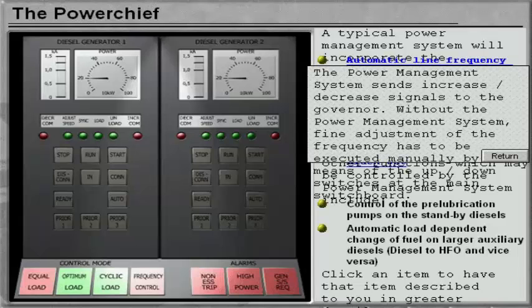The power management system sends increase and decrease signals to the governor. Without the power management system, fine adjustments of the frequency have to be executed manually by means of the up-down switches on the main switchboard.